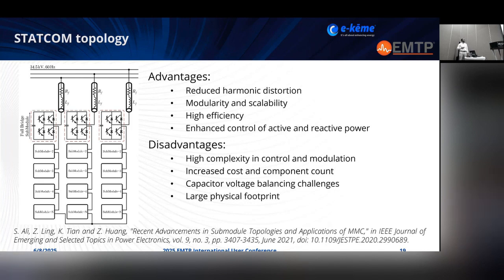However, this presents new challenges or disadvantages, like increased complexity in the control and modulation of the converters, and an increase in the cost or the number of components that compose this system. And capacitor voltage balancing represents a great challenge for this implementation, and affects the physical size of the system. And it's important to mention that in this case study, the modular converter is composed of 14 submodules and the nominal rated power is 50 MVAr.